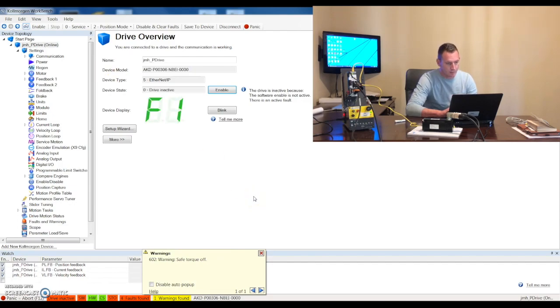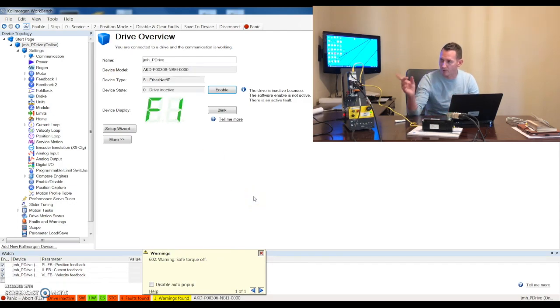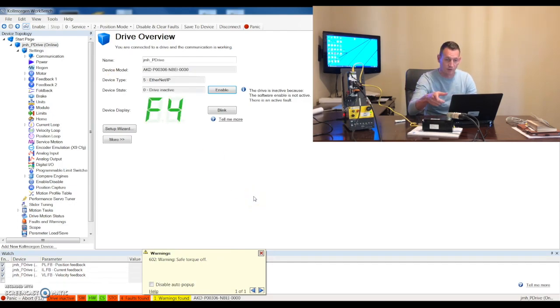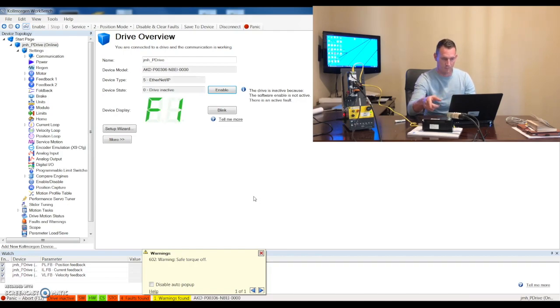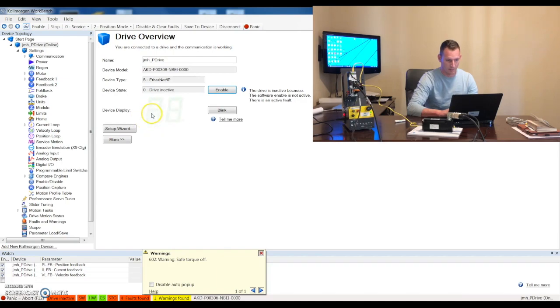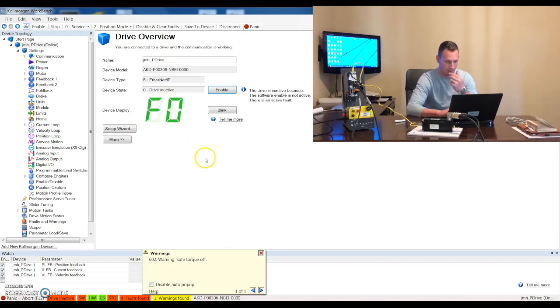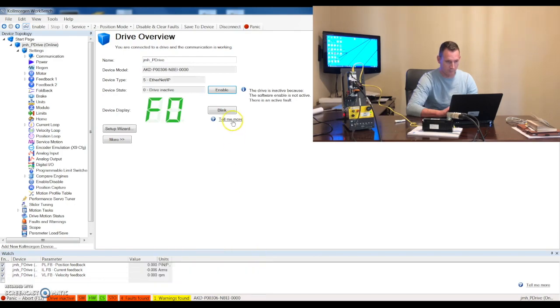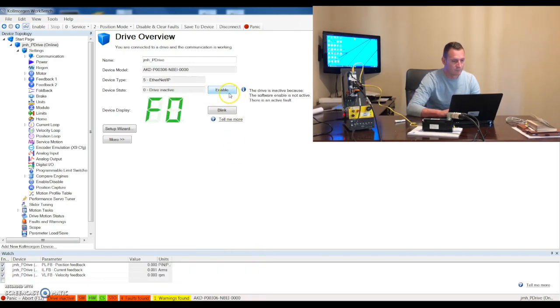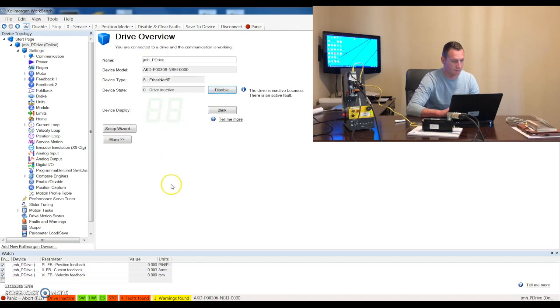And we'll go ahead and select connect. So workbench is going out connecting to the drive and it's reading the parameters of the drive. It's also reading the parameters of the motor since we have a smart feedback device on there. Now the faults that we talked about earlier you can see that they're displaying here on my device display so we'll be able to go ahead and clear those out. Let's go ahead and enable this drive.